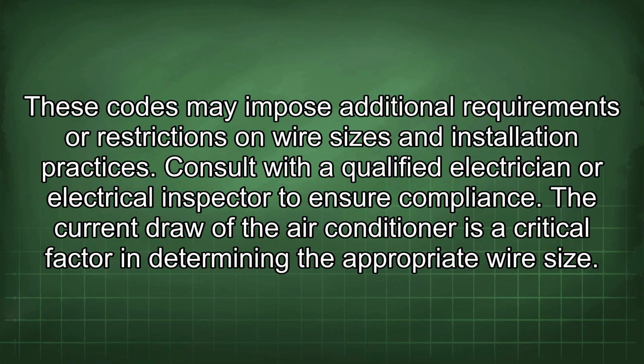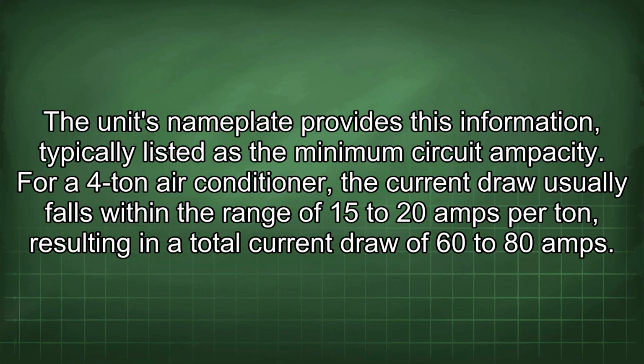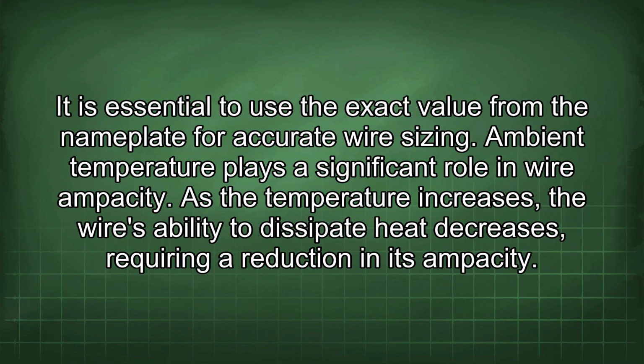The current draw of the air conditioner is a critical factor in determining the appropriate wire size. The unit's nameplate provides this information, typically listed as the minimum circuit ampacity. For a 4-ton air conditioner, the current draw usually falls within the range of 15 to 20 amps per ton, resulting in a total current draw of 60 to 80 amps. It is essential to use the exact value from the nameplate for accurate wire sizing.